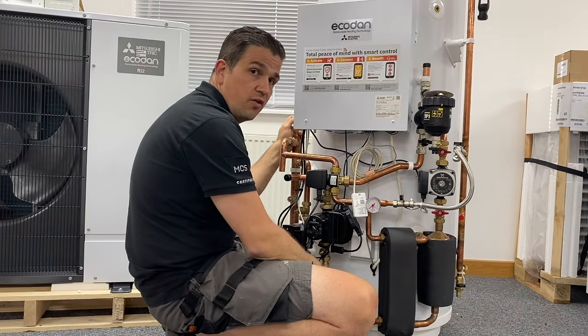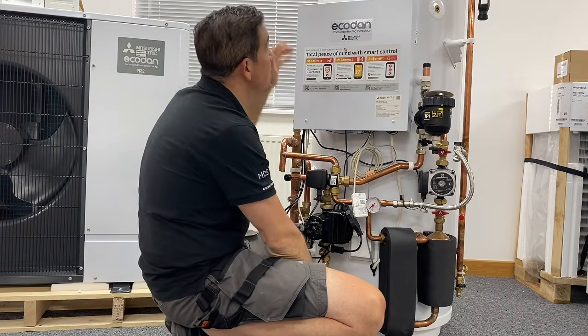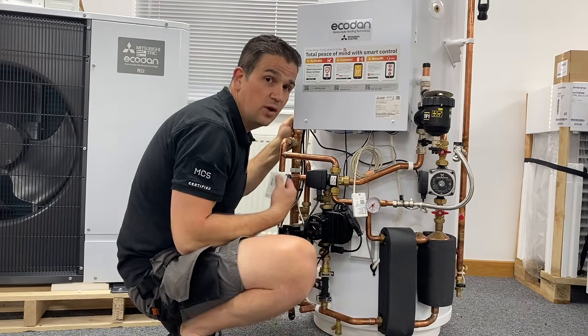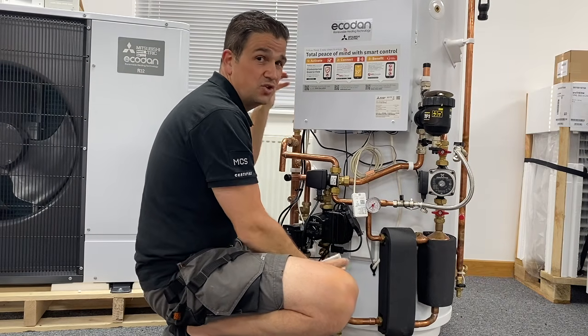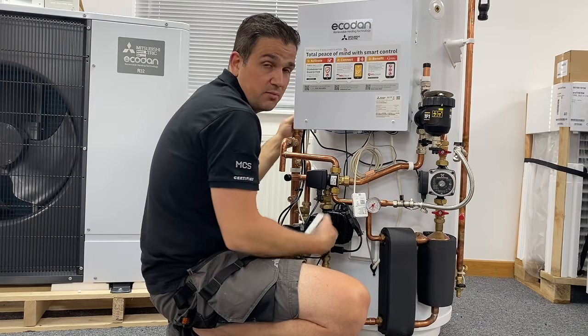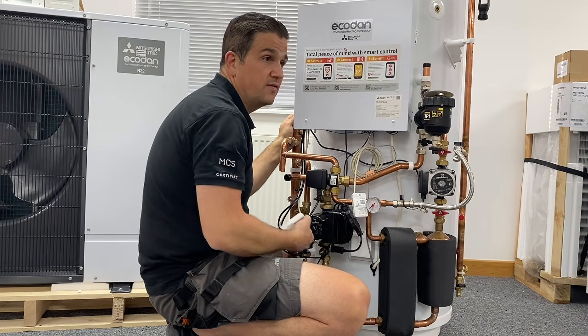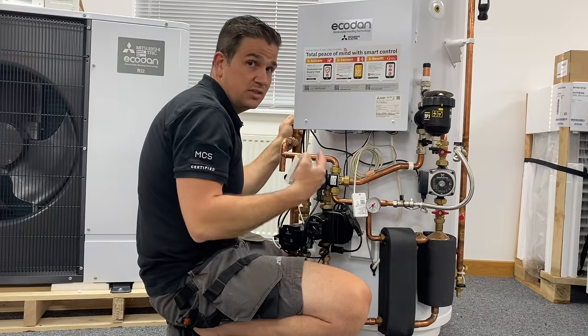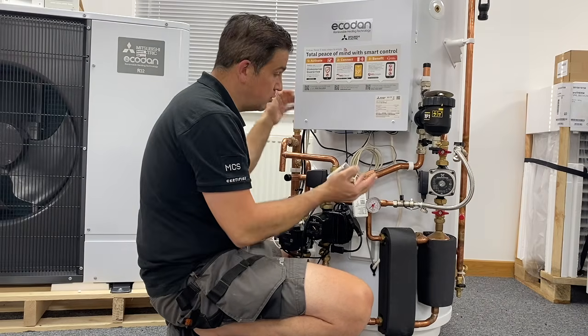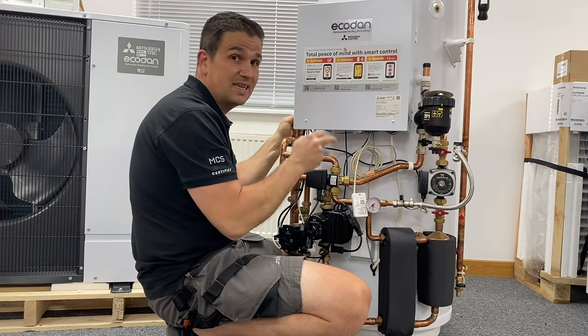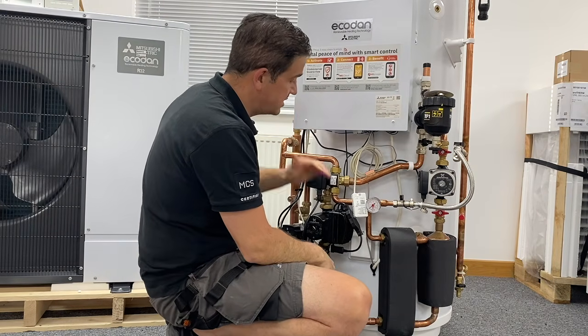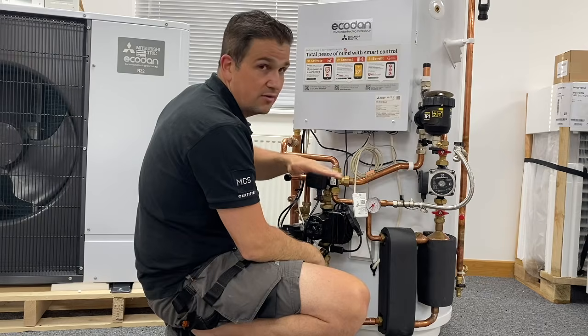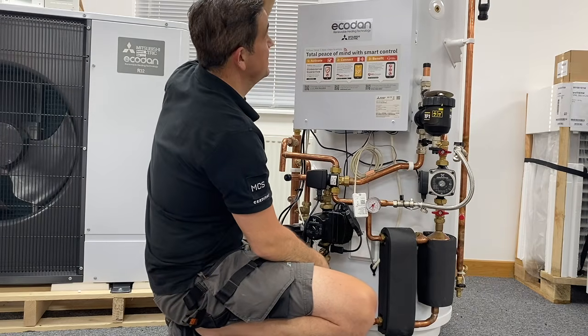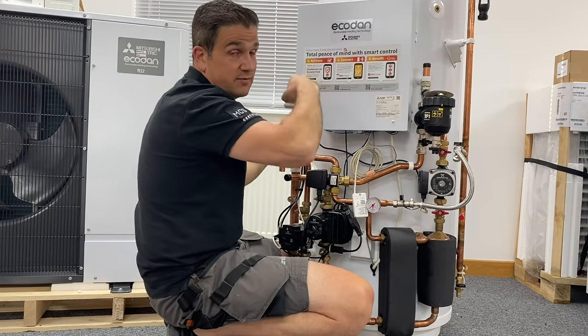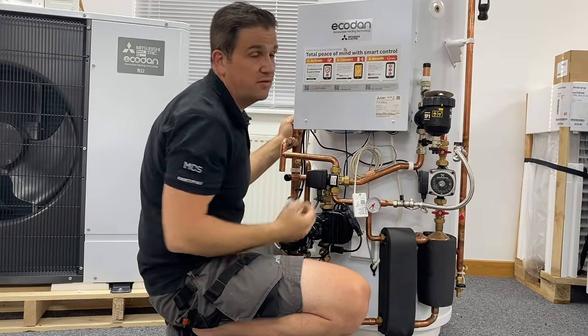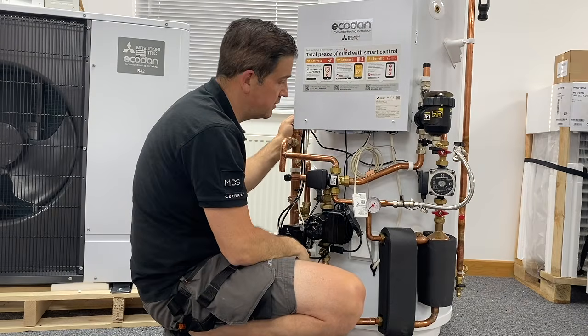If you've got a large family or a few bathrooms going off with everyone sharing at the same time, you've got a larger capacity, which means it will heat up and read off two thermistors. It's going to be slightly more in terms of charge time and how much energy it uses to generate that hot water, but it makes sure it fills a larger capacity with true hot water. At the set temperature down at this level, if it's say 50 degrees, you get stratification, and as you go higher up into the cylinder, heat rises, and it could be 53, 54 degrees the higher you get.